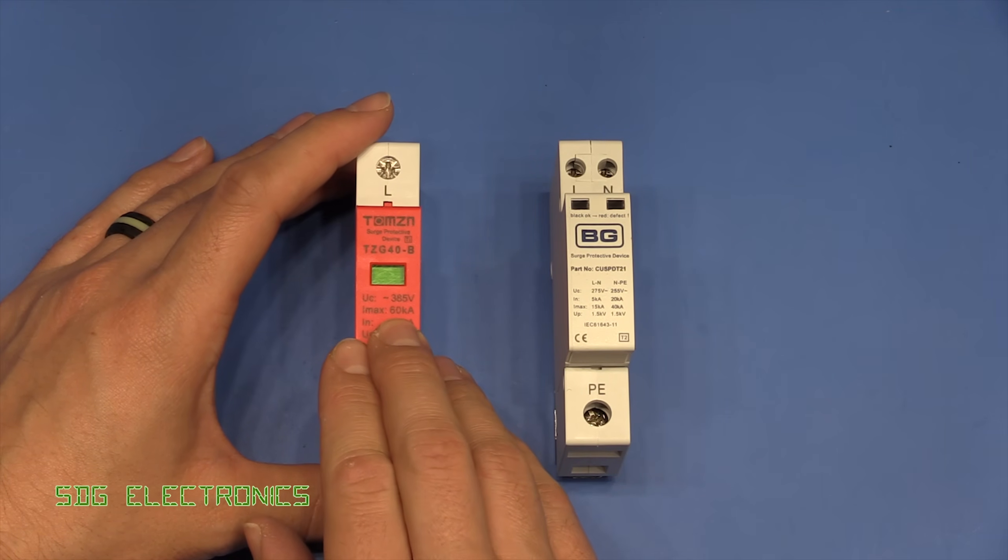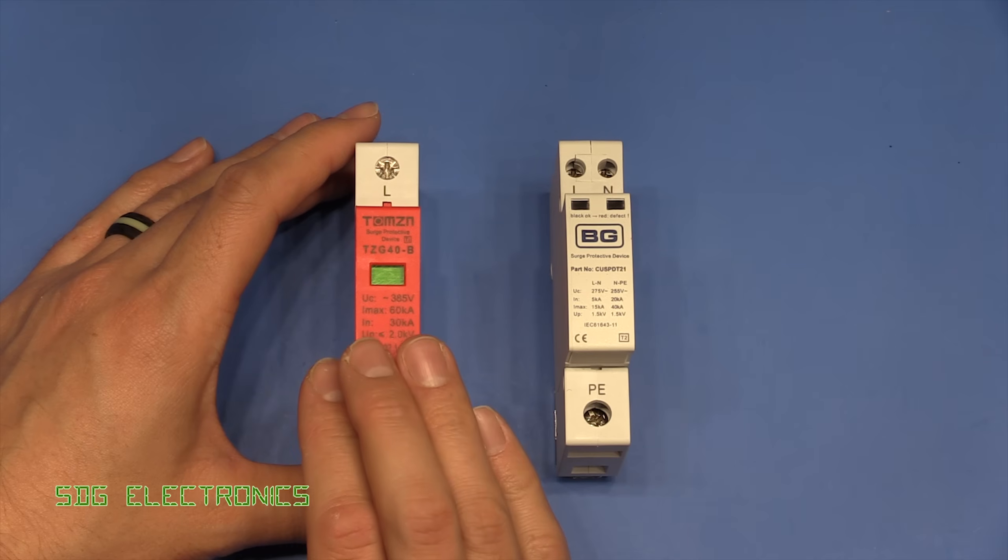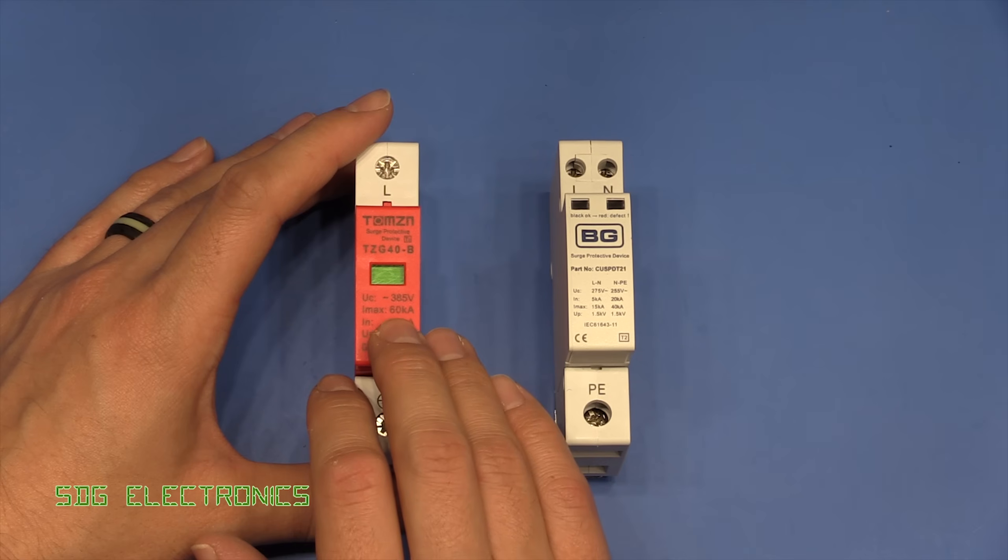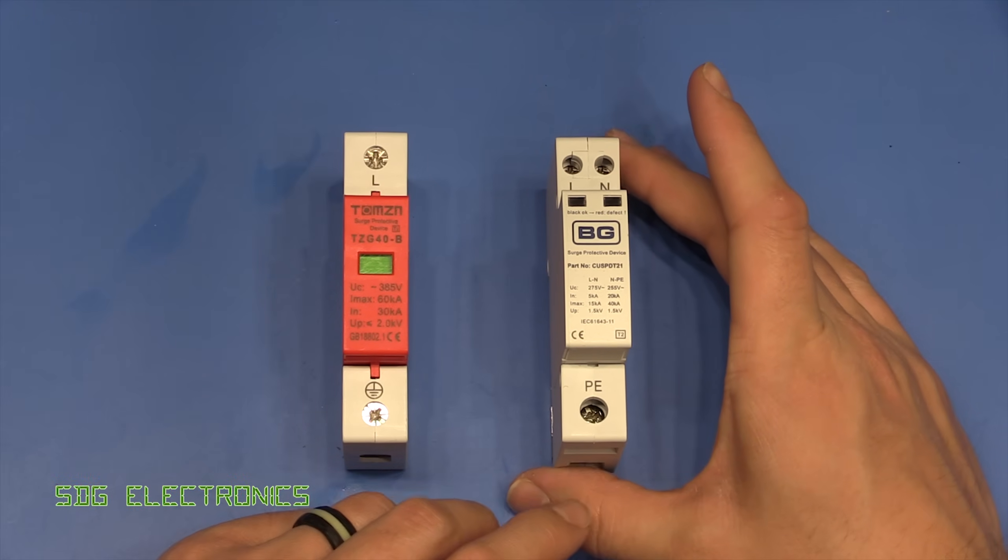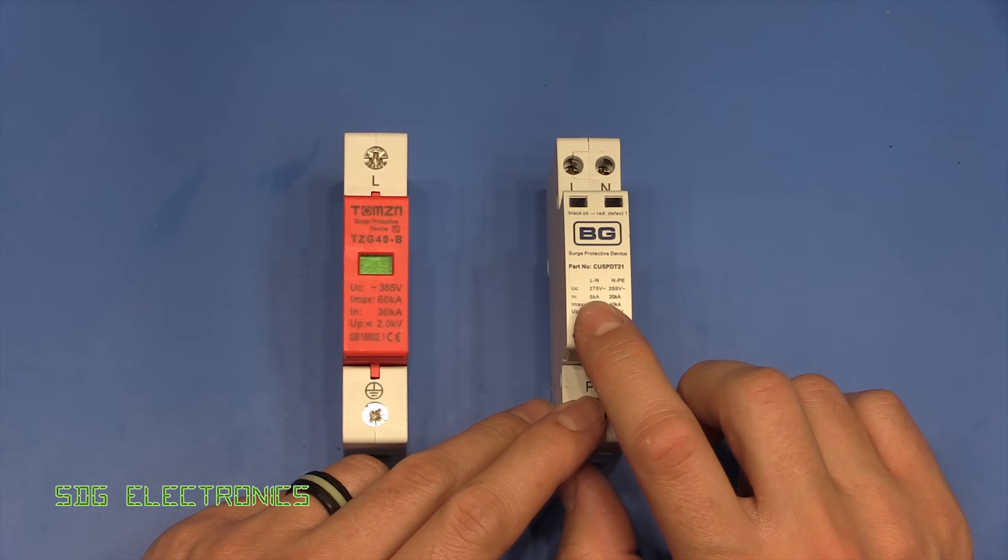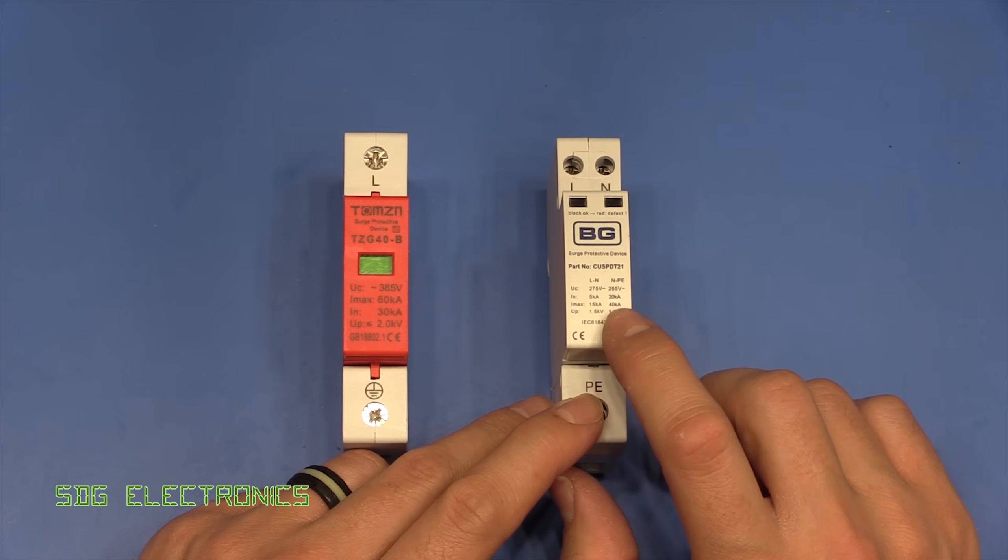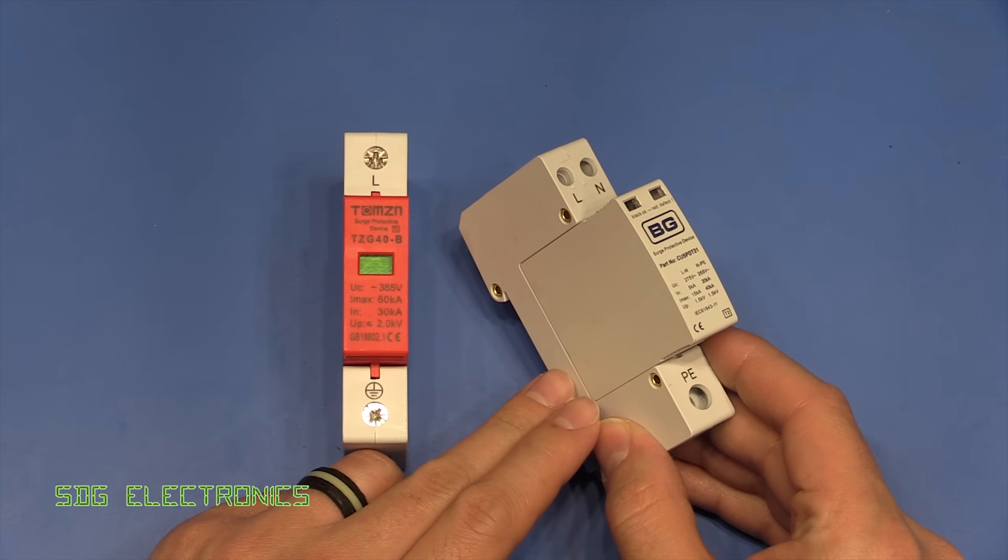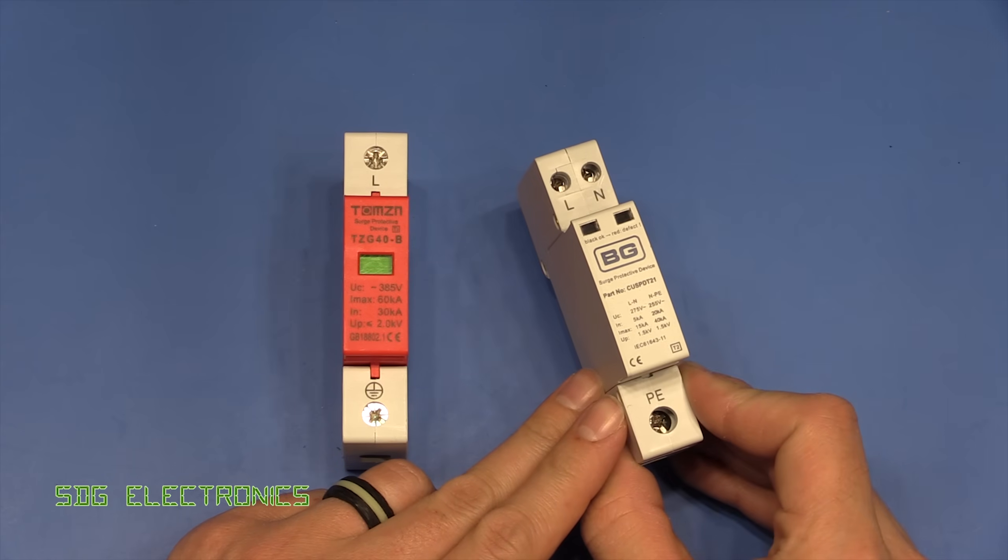So what I'm expecting in here is just maybe a large metal oxide varistor and possibly a gas discharge tube or something like that that can be used to shunt much higher currents. This one's rated up to 60 kilo amps, so a metal oxide varistor is not going to manage that, so there must be some other mechanism. On the BG device, it says from live to neutral it can support up to five kilo amp surges, which is most likely a metal oxide varistor - that's quite standard. Then between neutral and protective earth up to 40 kilo amps, so that's more likely to be your gas discharge tube. But even still, those components don't normally cost that kind of amount of money, so I'll be really interested to see what's inside this and how the two compare.